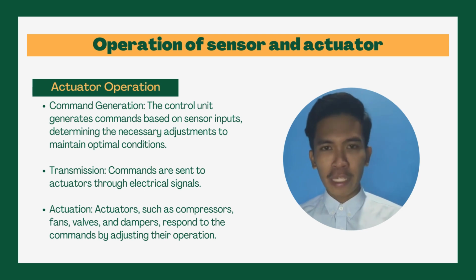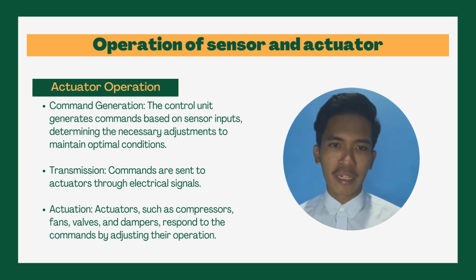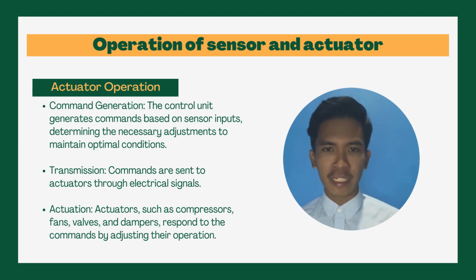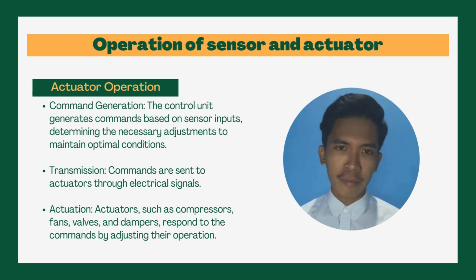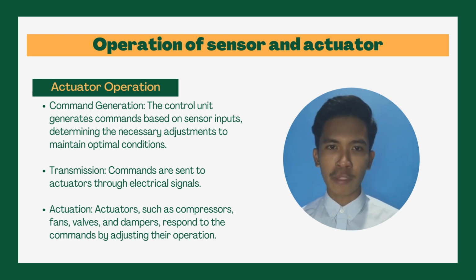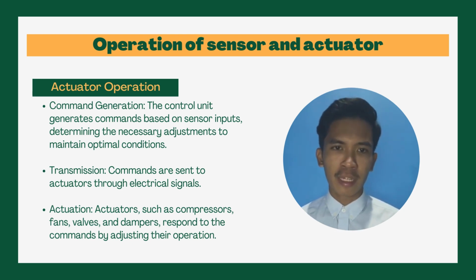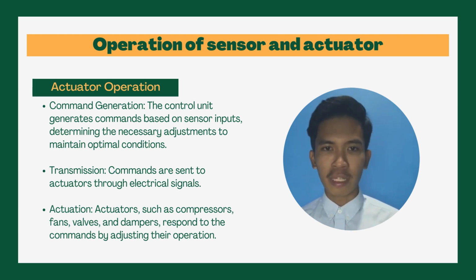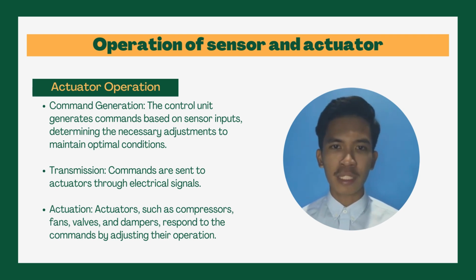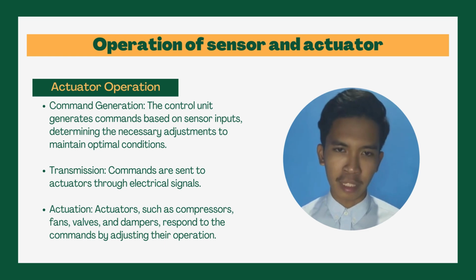Now we go to actuator operation. The first one is command generation. The control unit generates commands based on sensor input, determining the necessary adjustment to maintain optimal conditions. The next one is transmission. Commands are sent to actuators as electrical signals. The next one is actuation. Actuators such as compressor, fans, valve, and damper respond to the commands by adjusting their operation.